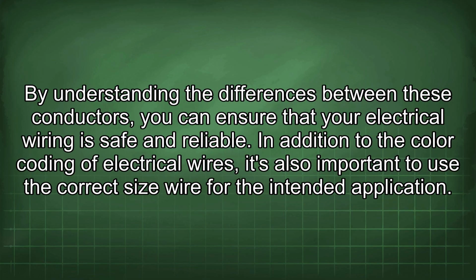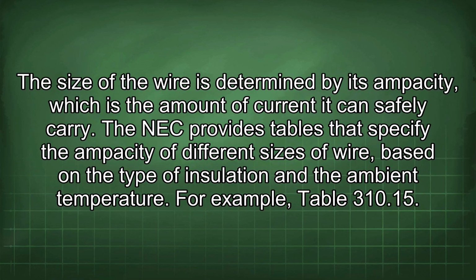By understanding the differences between these conductors, you can ensure that your electrical wiring is safe and reliable. In addition to the color coding of electrical wires, it's also important to use the correct size wire for the intended application. The size of the wire is determined by its ampacity, which is the amount of current it can safely carry. The NEC provides tables that specify the ampacity of different sizes of wire based on the type of insulation and the ambient temperature.